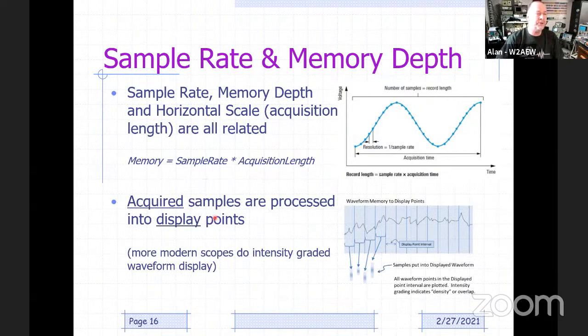So the acquired samples are then processed into display points. So I might have samples in memory that are much, much tighter in terms of interval than these samples that are going to be used for display. So most scopes will actually take the samples from the waveform memory and then compress them in some way to put them on the display. And in most cases with the modern digital scopes, they'll take all these samples that appear within a display interval, a pixel, if you will, and then maybe cloud them all into a whole column, if you will, of pixels in the display, and then again and again, and then kind of do an intensity grade to kind of emulate what the phosphor did on the old analog scopes to give you kind of an intensity graded display.